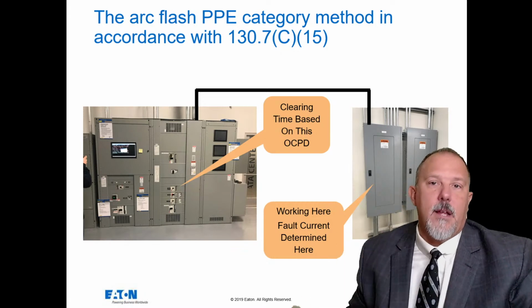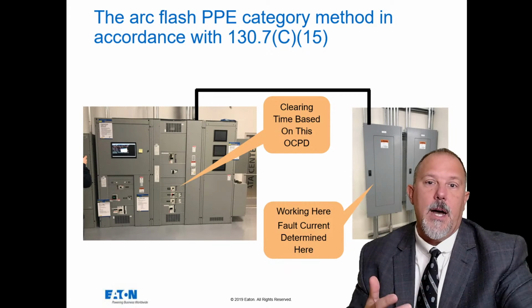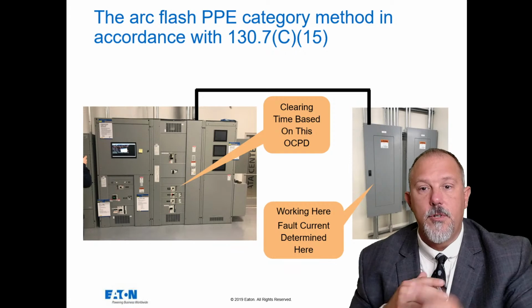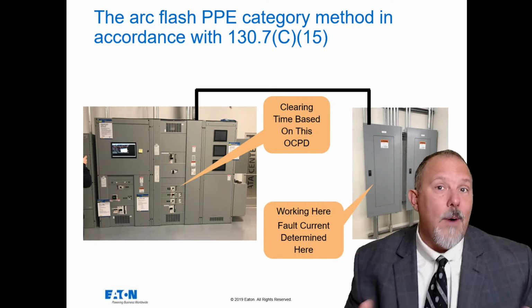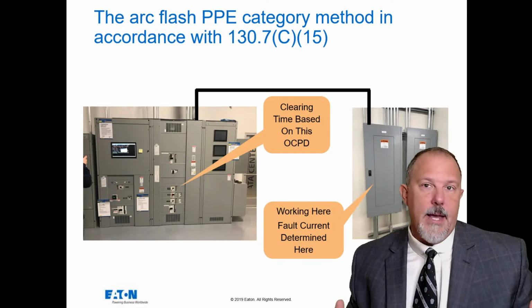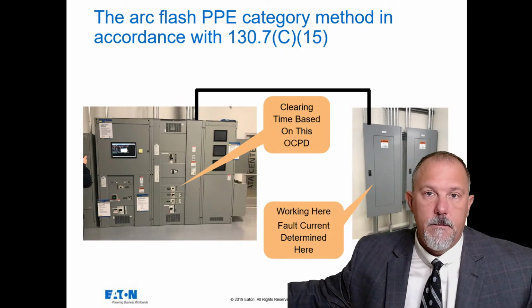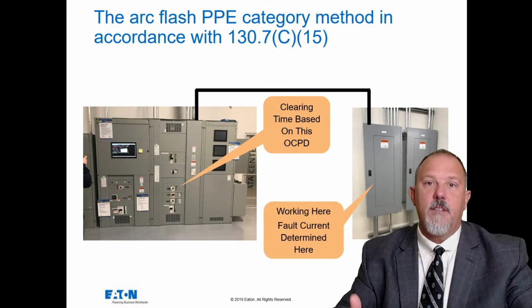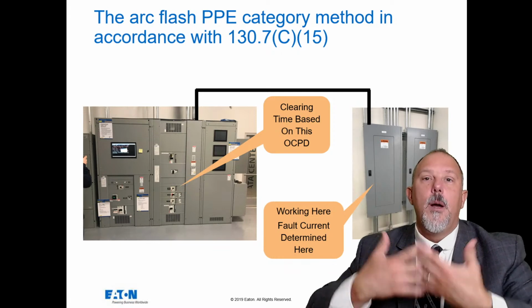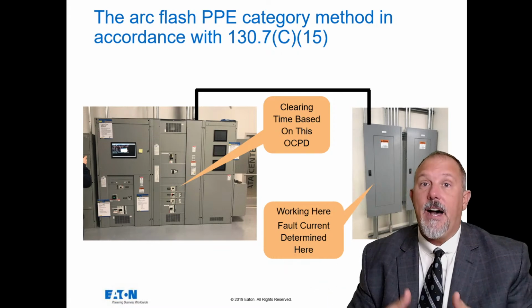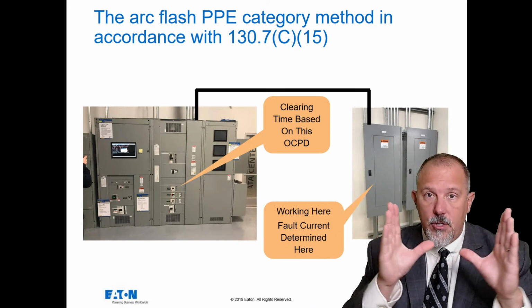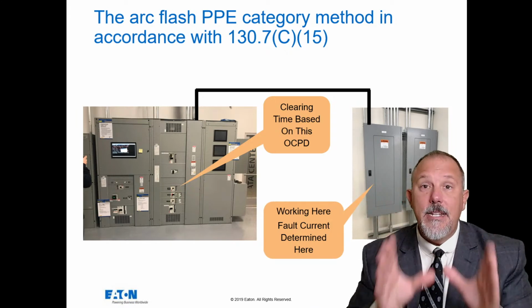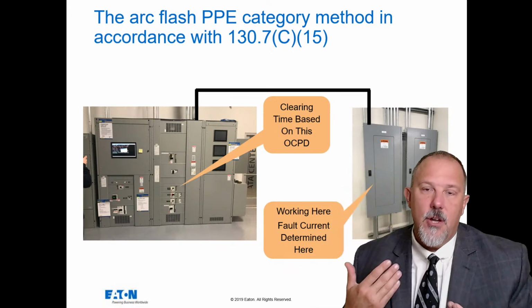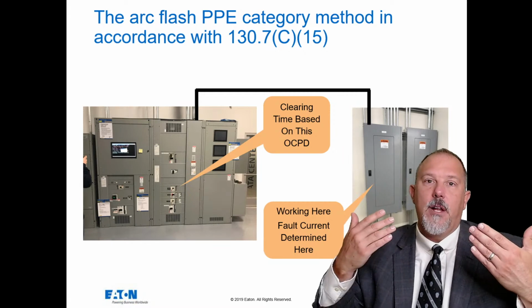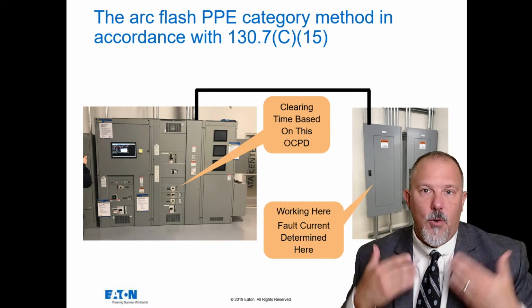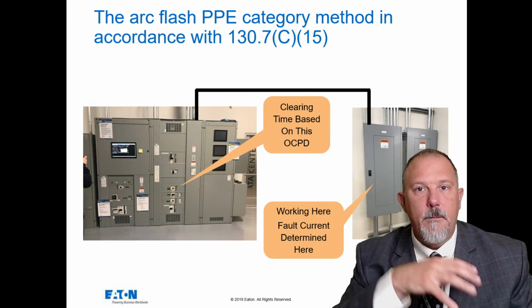I'm not wearing a balaclava. I'm wearing gloves, because when I reduce the incident energy, I'm not only reducing the incident energy, I'm reducing my arc flash boundary. Why is that important? If I've got, say, 28 calories and my arc flash boundary is in feet, my entire body is in the arc flash boundary. My entire body needs to have personal protective equipment. If I can reduce the incident energy and reduce the arc flash boundary, my arc flash boundary could be inches. And now my head is not in the arc flash boundary. I may not even have to have a balaclava. I might be able to get away with lighter and lower rated personal protective equipment.